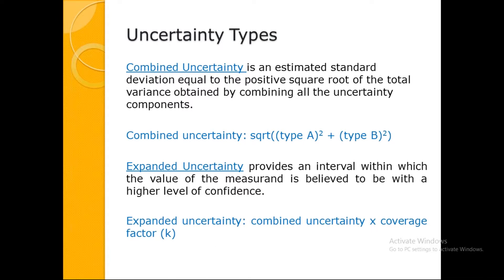Combined uncertainty, as the name suggests, combines all uncertainties — Type A and Type B. The formula is the square root of (Type A squared plus Type B squared). Type B may have multiple contributing factors — volume, balance, CRM — all must be squared and added to Type A squared, then the square root taken. Expanded uncertainty provides an interval within which the value of the measurement is believed to lie with a high level of confidence. Expanded uncertainty equals combined uncertainty multiplied by the coverage factor.